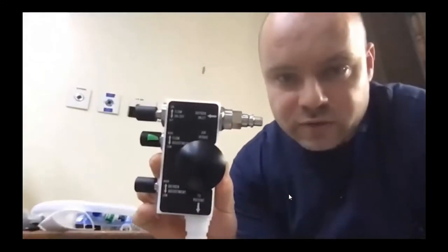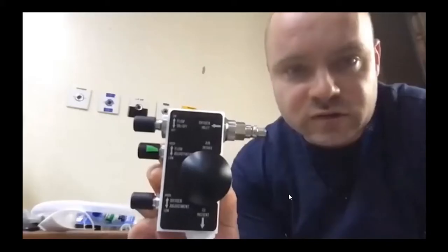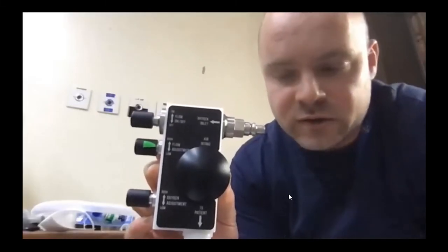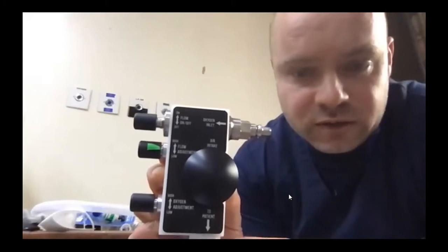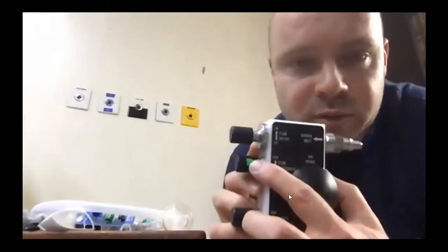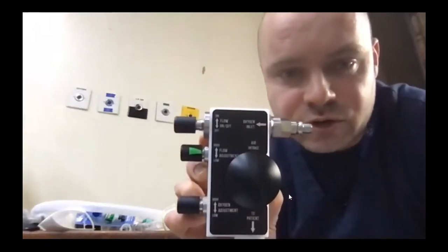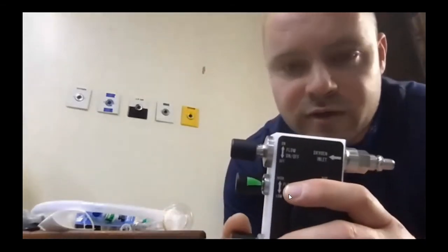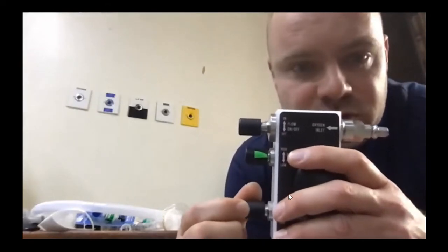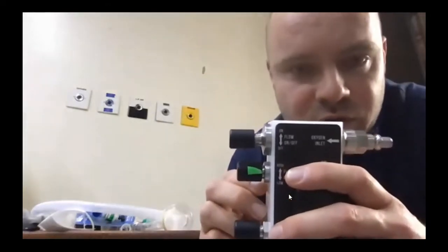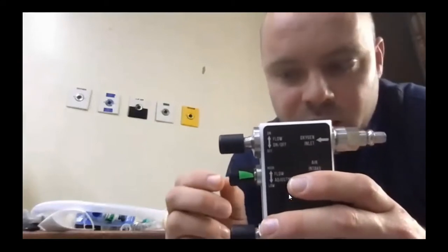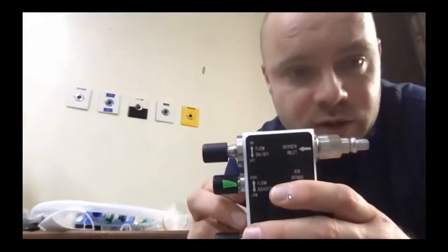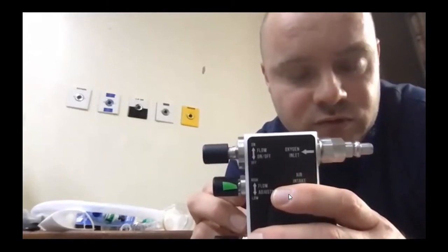The device itself, you should have this exact one made by SaberTech, which is essentially the UCL device. The only thing I've done to it, just to make the explanation a little easier, is in the off position on the knobs, I've put a little bit of tape onto the flow control knob, and on the FiO2 knob, I'm just using the small screw that's in it to determine how many turns we're going through, just to give you an idea of how far to go, and equally how sensitive the turns are.